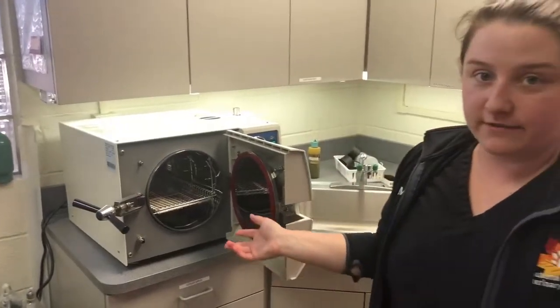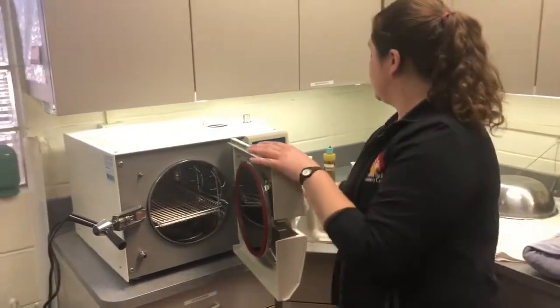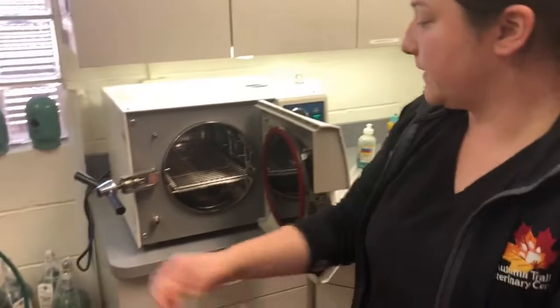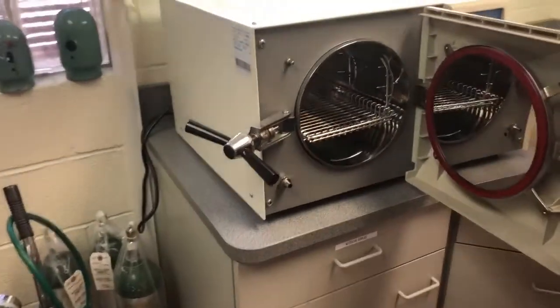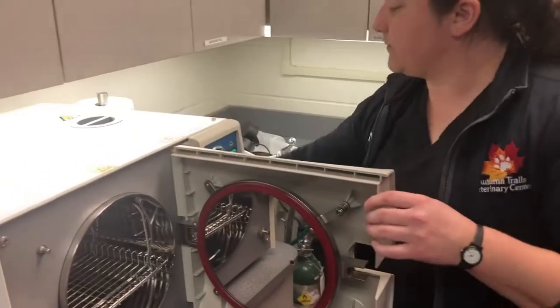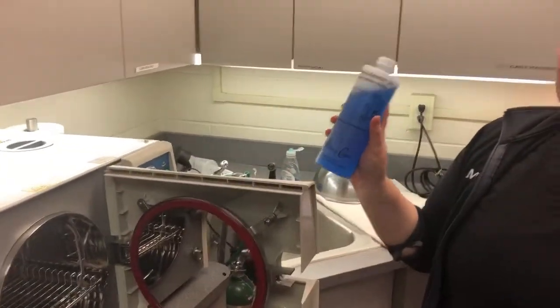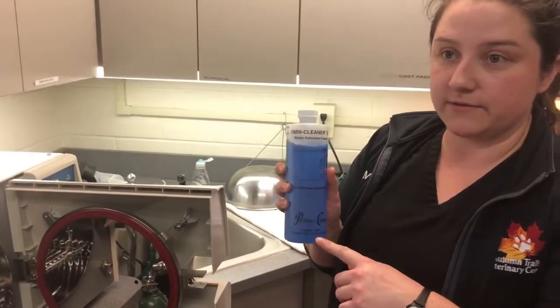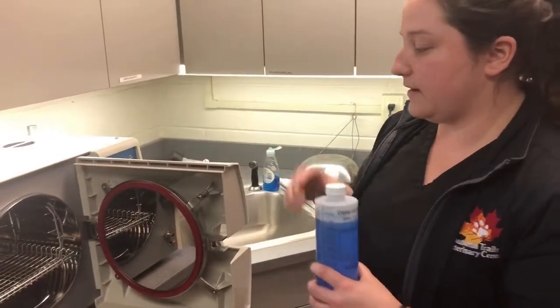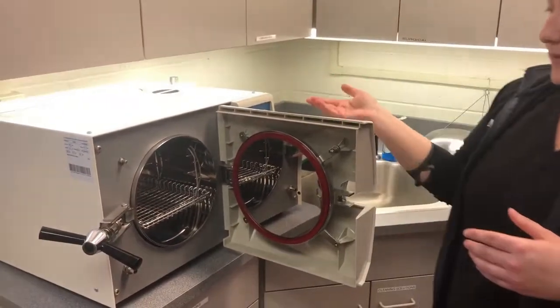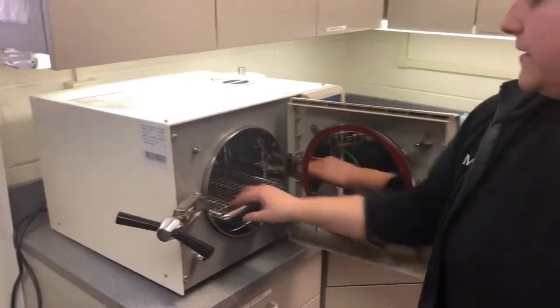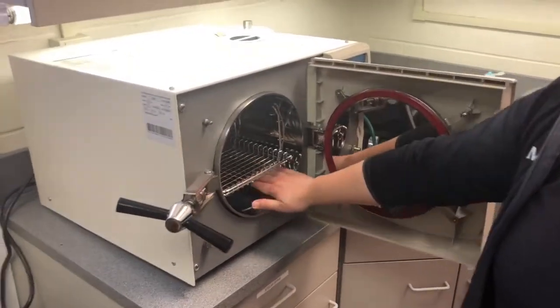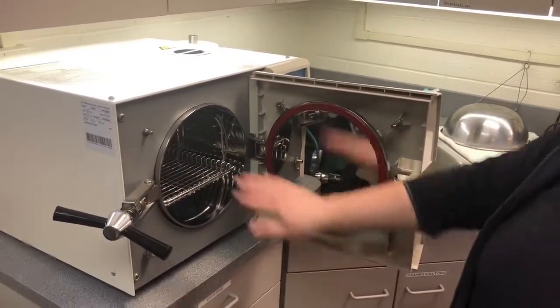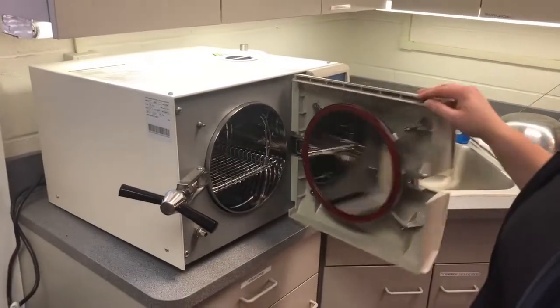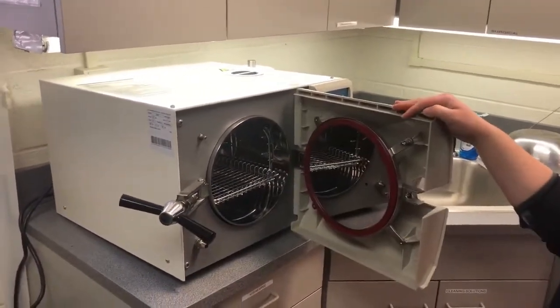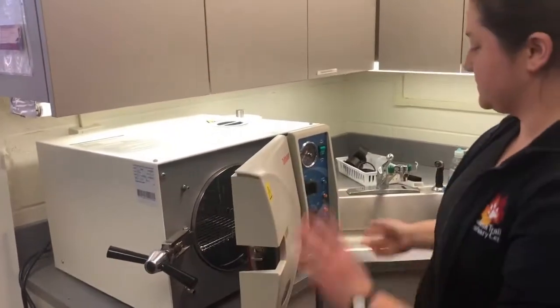So as far as autoclave maintenance, once a month, we take this tube, hook it up right here to this outlet, and we drain all of the distilled water out of the machine. Then we run one cycle with this autoclave cleaner. So this is diluted with distilled water. We run a cycle with that, and then drain that as well and refill it with distilled water. And then we also take the trays out and use a damp cloth to clean out the inside, clean the doors, clean the top, make sure that there's nothing in the way, nothing's rusty, nothing's broken, everything's functioning appropriately.